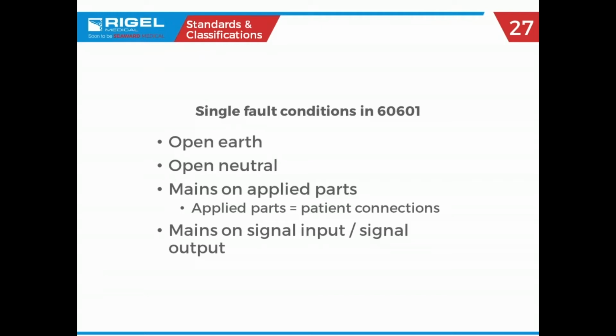So we'll take 110 or 220 volts and put it on those EKG leads and make sure they're not electrically breaking down at line voltage. They never see line voltage in operation, but that's how it's tested under the 60601. And you go through every one of those. A lot of safety analyzers have the 60601 test standard built into them.